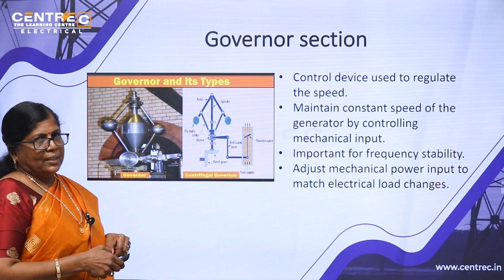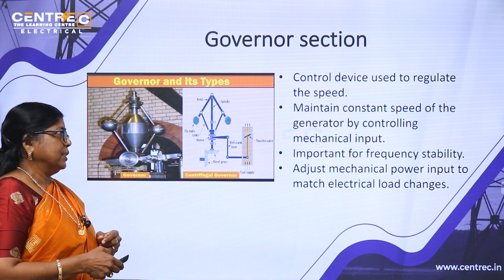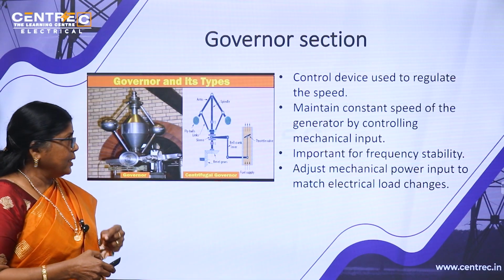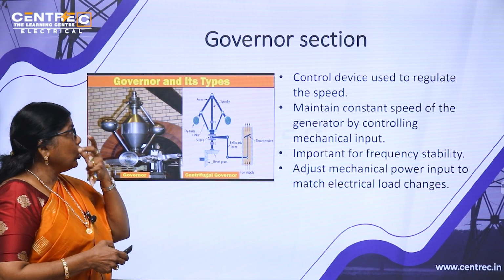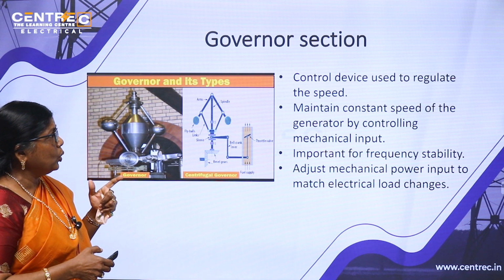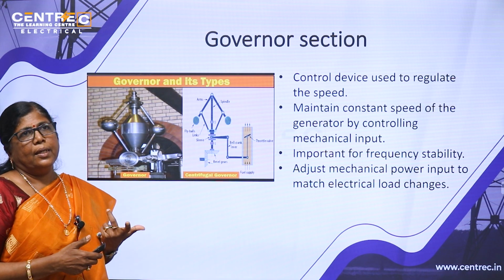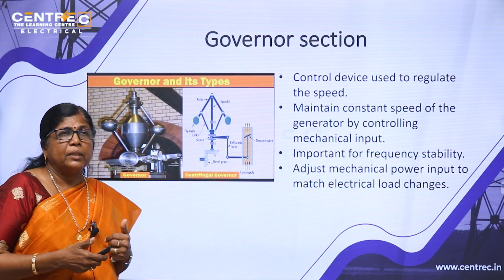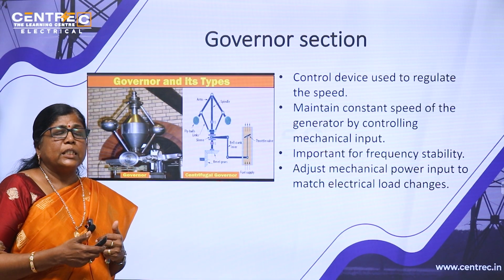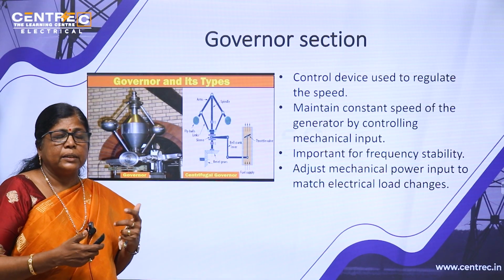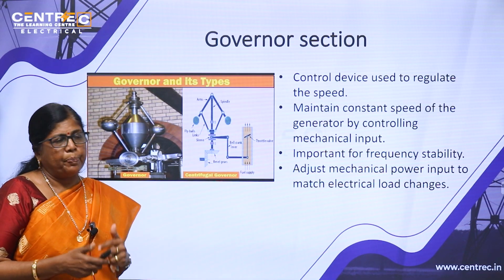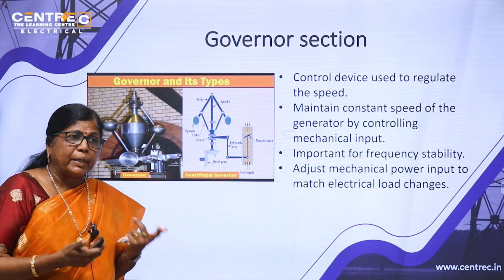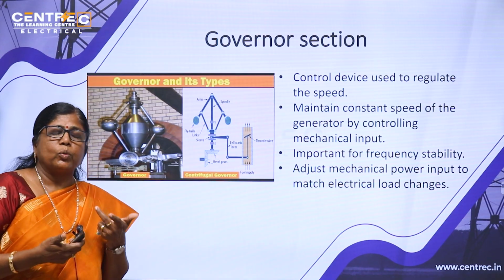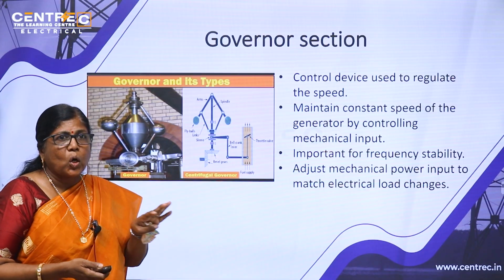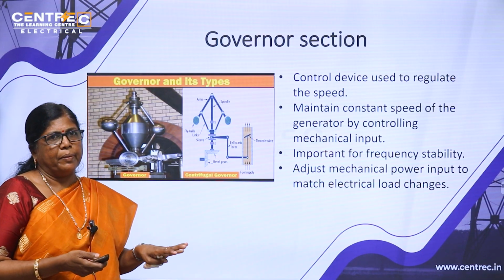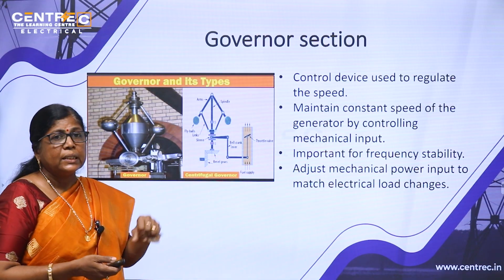Then the governor section. The governor section is an important section in all power stations, because all the control devices, that is, the control device used to regulate the speed. For example, in the Mulamattam generating station, the speed of the turbine and generator is 375 RPM. Whether it generates 30 megawatt, 40 megawatt or 130 megawatt, the speed remains constant at 375 RPM. That can be achieved with the help of this governor.